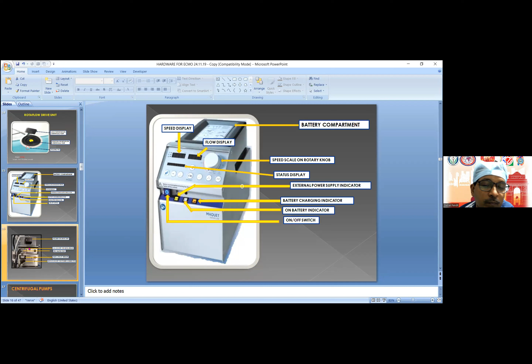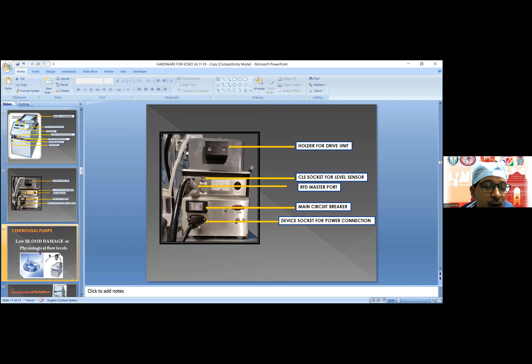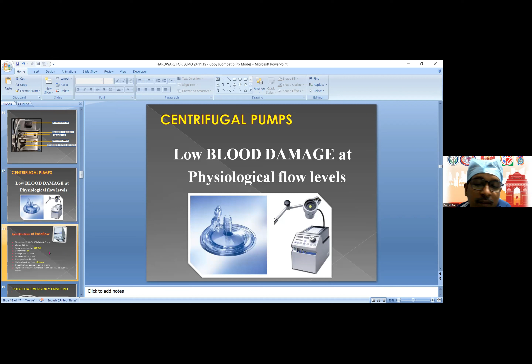This is the backside of the machine. This is the power system, and this cable carries the instruction to the Rotaflow drive unit. As a whole, this is the disposable pump, and it is coupled with the machine, with the drive unit, without any contamination. It is connected to the tubing and working nicely. If we go to the configuration of this console, it requires 220 volts, with wattage like one ceiling fan, a maximum current consumption of 8 ampere, and it has a battery backup of 1.5 hours. The whole system works through the battery, so we cannot remove the battery and start the console. It's basic information for everybody.